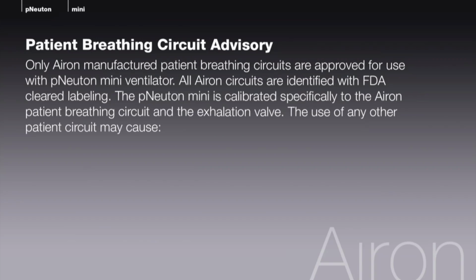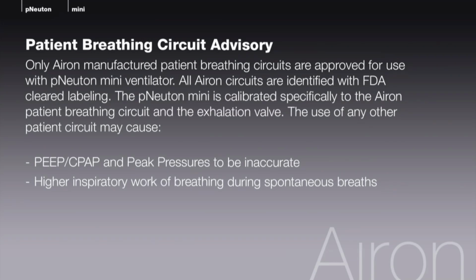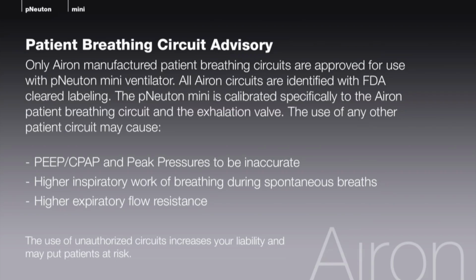Please note, only Airon manufactured patient breathing circuits are approved for use with the pNeuton mini ventilator. All Airon circuits are identified with FDA-cleared labeling. The Mini is calibrated specifically to the Airon patient breathing circuit and the exhalation valve, and the use of any other patient circuit may cause PEEP CPAP and peak pressures to be inaccurate, higher inspiratory work of breathing during spontaneous breaths, and higher expiratory flow resistance.